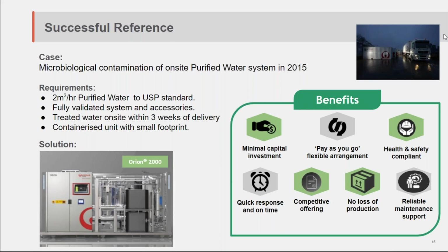So they contacted us and we offered our mobile Orion unit, which is a softening RO EDI system for purified water production. And the advantage of this unit was that it is hot water sanitizable, which helped mitigate the issues with microbial contamination. So we provided the mobile Orion unit, which, as I say, overcame this issue.